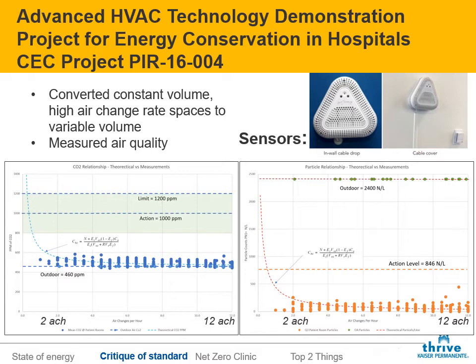So we put sensors on the wall and tracked temperature and humidity and VOC and CO2 and particles. And we wound up with a pretty huge data set. 73 locations we put these sensors in, and we have 6 months worth of data. So there's 8 million data points. And the charts that are on this slide come from the patient rooms. You can see 2 air changes on the x-axis and then contaminants on the y-axis.